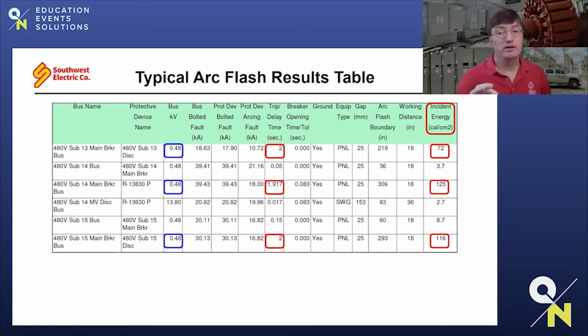480 volts is 99 times out of 100 going to be the equipment that has the highest arc energy for any simulation, any assessment. You would think the higher voltage equipment would be more dangerous when it comes to arc flash. Actually, it's the 480 volt ends up being the most dangerous. That doesn't mean that all 480 volt equipment is dangerous, but based on conditions, based on event available energies, based on the protection, and that's the key, is the protection at 480 usually is not sufficient to pick up these lower arc fault current values. And because those are delayed, they build up into these high energy levels.